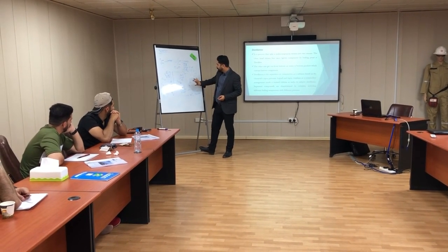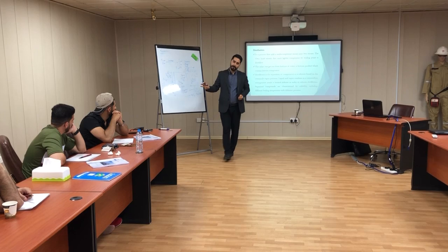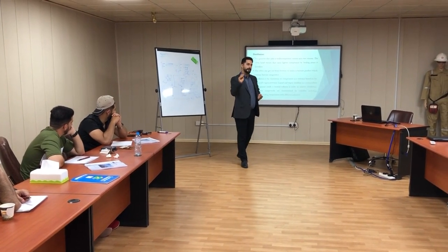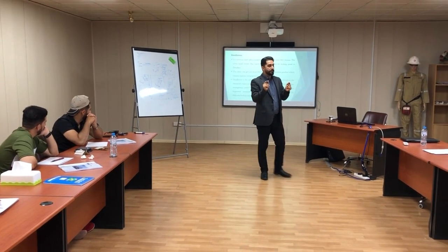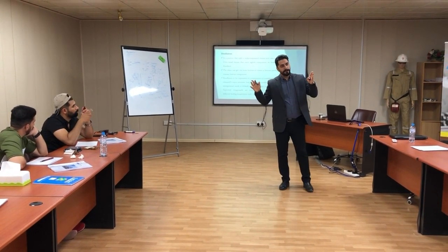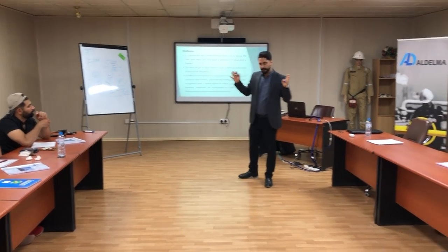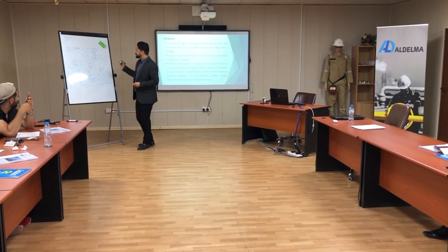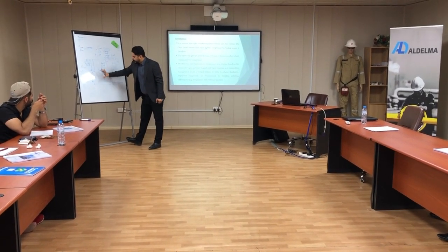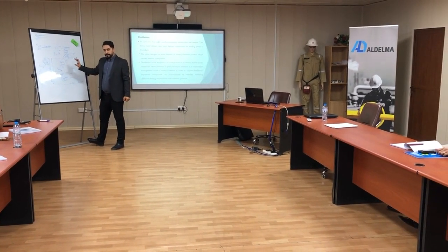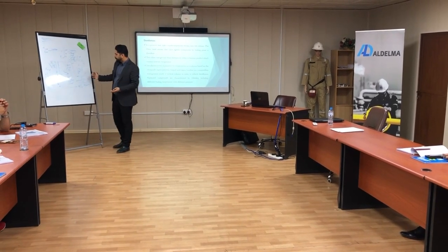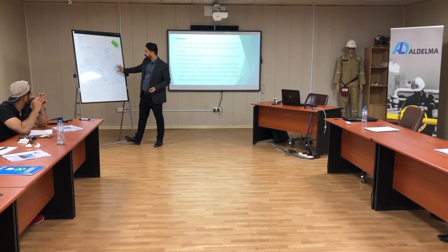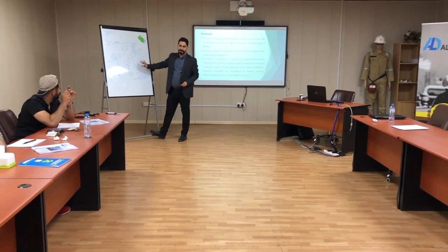And always I try to increase the reflux as much as possible. But I should consider the flooding and entrainment phenomena that we have spoken about. Do you remember? We'll talk about it again in the next slides. But for a typical distillation column, I always have this configuration: a reboiler at the bottom, a condenser and a reflux pump at the top section.